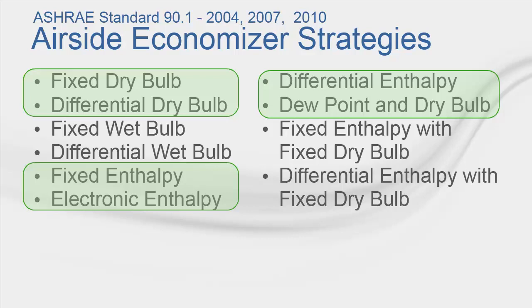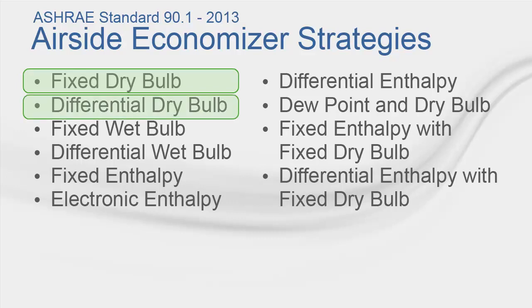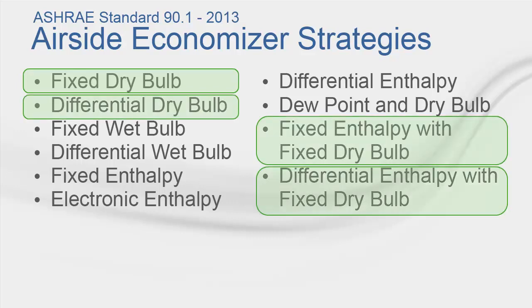The committee's explanation for this exclusion can be found in the foreword to addendum DW of Standard 90.1-2010. The four types allowed by Standard 90.1-2013 are the fixed dry bulb, differential dry bulb, fixed enthalpy with fixed dry bulb, and differential enthalpy with fixed dry bulb methods.